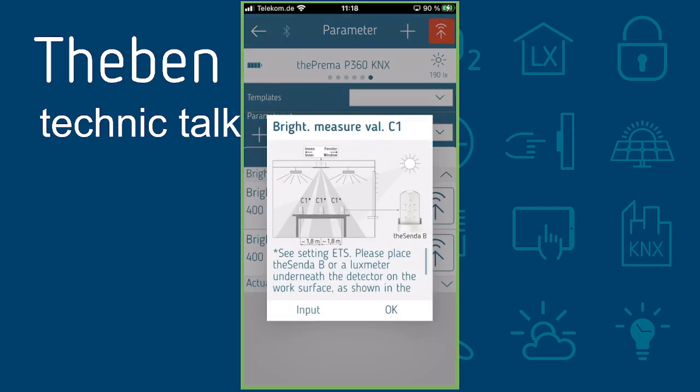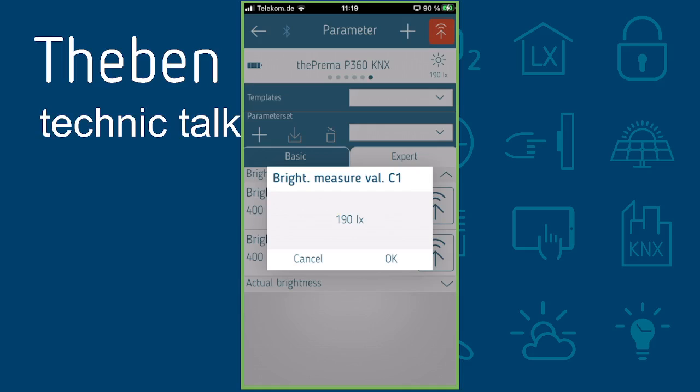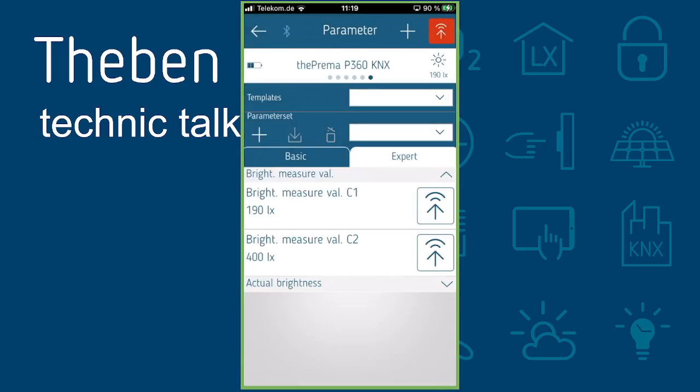Opening this menu again gives you a reminder on where to position the theSenda B. Confirm by pressing OK. The app reads the current value — in our case 190 lux. Press OK, then press the orange button on the top right to convert and transfer the value. The calibration is done. Hope to see you next time, bye!